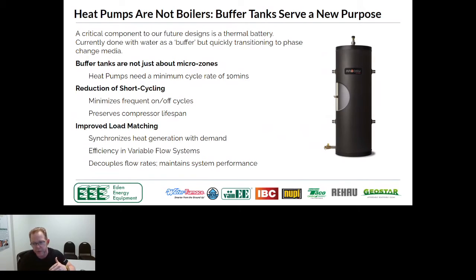As that heat pump starts up, it's going to ramp up and then it's going to find its sweet spot, its modulation point. So for example, if my air to water goes to 90 hertz, the compressor is going to fire up to 60, 70 hertz. It's going to find about where it's at based off the supply temperature and what we're targeting and what the return temperature is, and it's going to modulate to find its most efficient spot. So from a wear and tear standpoint, we don't want the equipment banging on and off repeatedly. But on top of it, if we can let the unit run for 10 to 15 minutes, not 30 seconds to 1 minute, it has a significant impact on the performance of the unit.